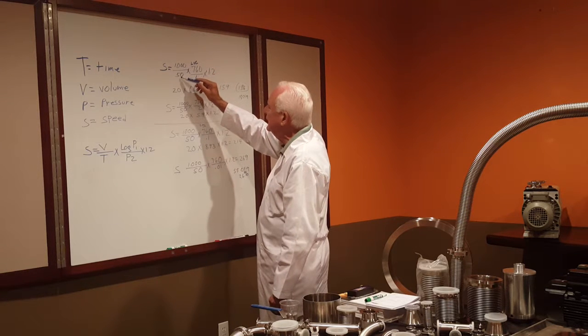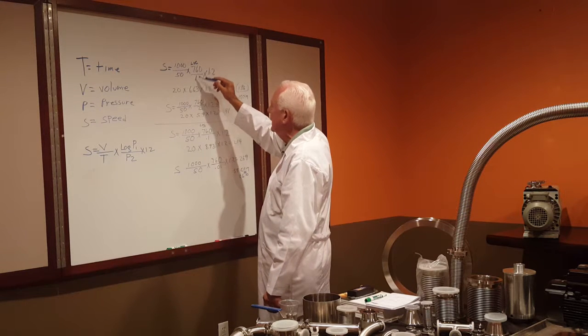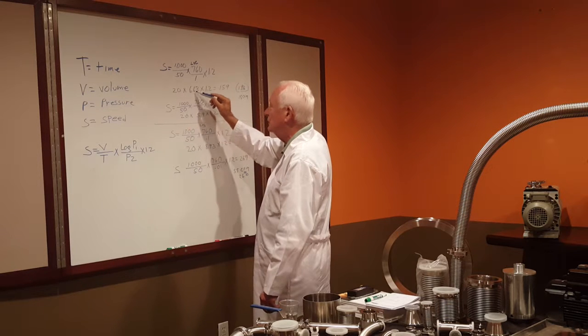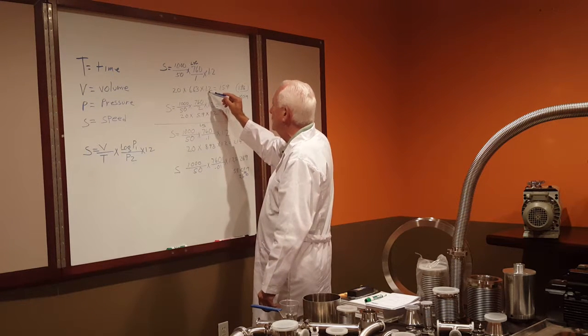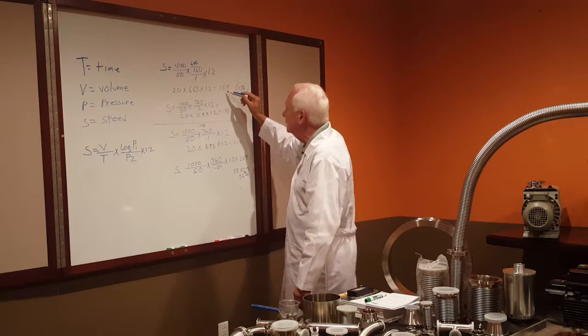As an example, I've taken a 1000 cubic foot vessel and I want to get down in 50 minutes. I'm starting at atmosphere and I want to go to 1 torr. So that's 20 times the log of 760 over 1, times 2.3 — so I need 159 CFM.